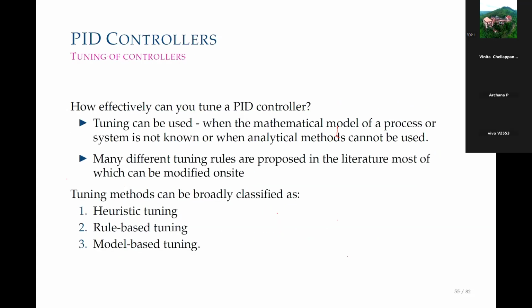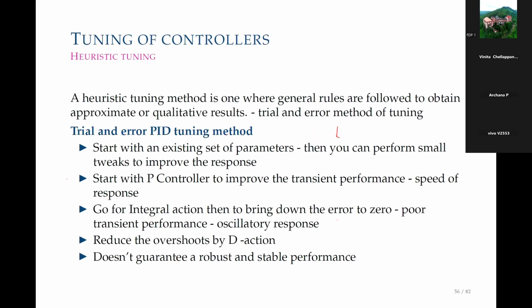Now there are other important techniques for tuning Kp, Ki and Kd: heuristic tuning, rule-based tuning, or model-based tuning. In heuristic tuning, we just define the Kp values of the system initially, tweaking it as we define the P controller in the way we saw earlier. First we plug in the P controller to improve the speed of response, then go for an integral action to bring down the error to 0. But we get a poor transient performance and an oscillated response, so we then go for a D action if required. This heuristic tuning does not guarantee robust or stable performance.